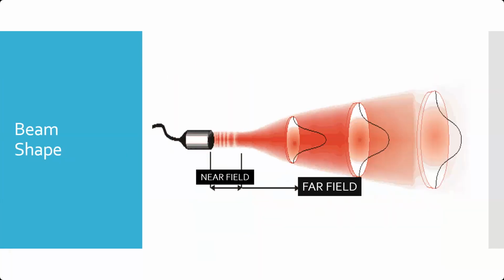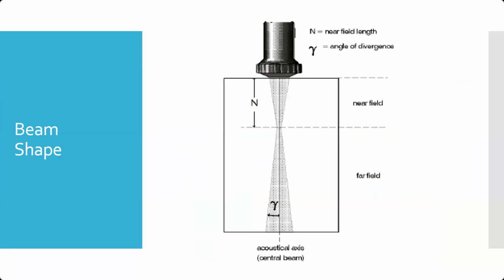Here's another kind of representation of what the beam looks like coming out of one of these ultrasonic transducers. There's that near field showing all that interference taking place, and then the far field where you have more consistent wave fronts, beam fronts that are used for testing. If we look at it with a probe that's on a part, it looks something like this, and now we can figure out our near field length and the angle of divergence based on the properties of the sound that we're using.